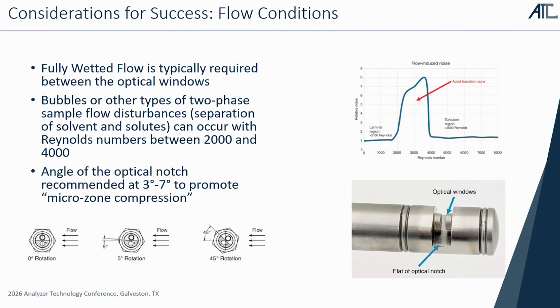Fouling on the probe isn't good, right? Because then you're going to have to increase your service maintenance. So just something as simple as how we clocked this probe into the process can make the difference between your $50,000 analyzer working or not working.